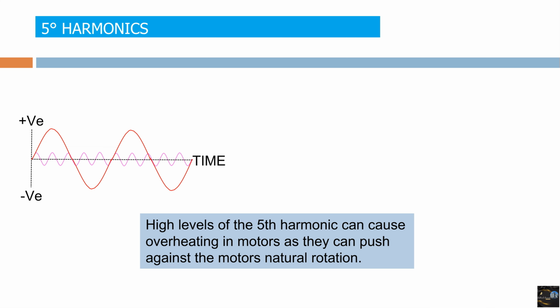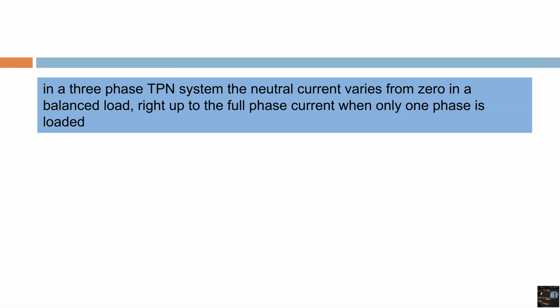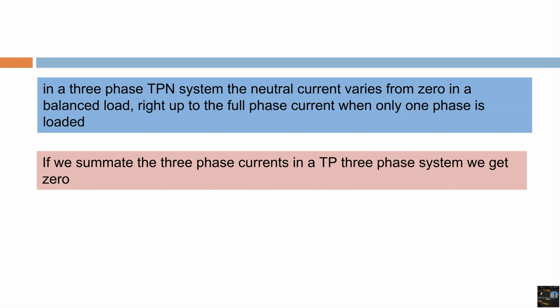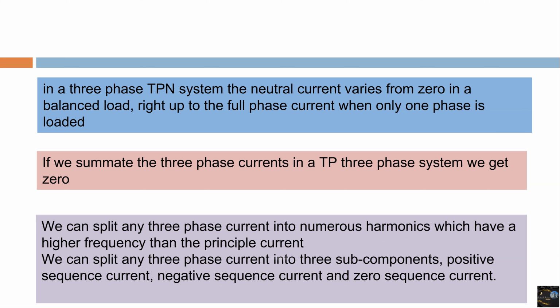In a three-phase TPN system, the neutral current varies from zero in a balanced load right up to the full phase current when only one phase is loaded. If we summate the three-phase currents in a TP three-phase system, we can get zero. We can split any three-phase current into numerous harmonics which have a higher frequency than the principal current. We can split any three-phase current into three subcomponents: positive sequence current, negative sequence current, and zero sequence current.